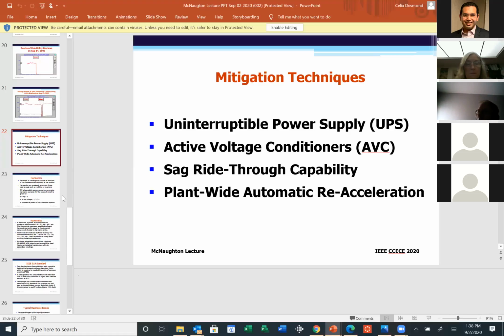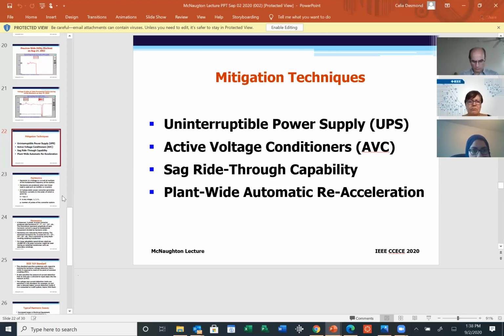The last one is what we call plant-wide automatic reacceleration. Consider a refinery that typically has 500 plus motors. Then you have a voltage sag, or even a momentary loss of power. That's a good word, momentary loss of power. What is going to happen? You're basically going to lose almost all these motors. Can you imagine operators running around, trying to restart these motors manually or even from the control room? And they have to be started in a specific sequence. It's not up to you, A, B, C, D. So in this particular case, I was engaged where we implemented plant-wide automatic reacceleration using PLCs. And we did this work, believe it or not, in 1992 for a refinery right here in Ontario. It was a very successful implementation.